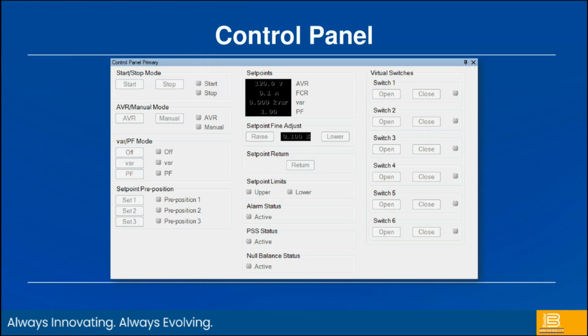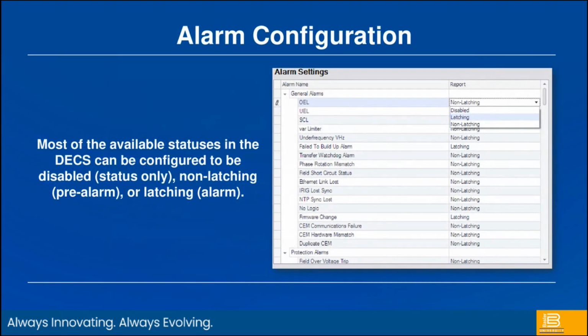Control panel. This will pop up in the metering screen of BESTCOMS. So remotely, I'll be able to do start, stop. I can change modes of operation. I can control virtual switches, breakers to do other things as I tie them into logic. Gives me a status indication of what modes I'm in, if I want to raise or lower set points. All of that done from the BESTCOMS Plus software. You can set up alarms. We can set those up for basically disabled alarms, or we can set up for latching or non-latching alarms. So latching alarms, once they happen, they're going to stay there until they're reset. A non-latching alarm will just be present when that condition is present.